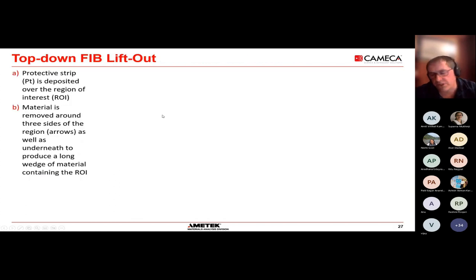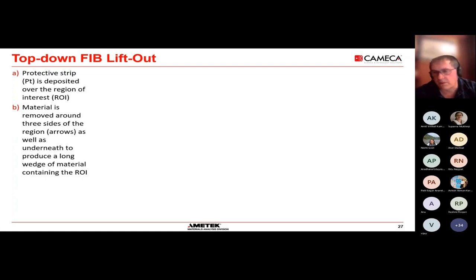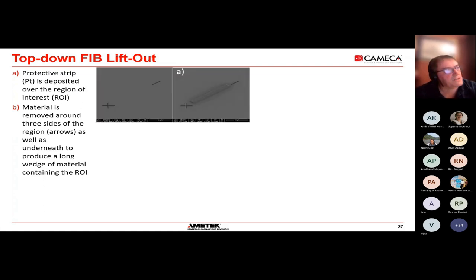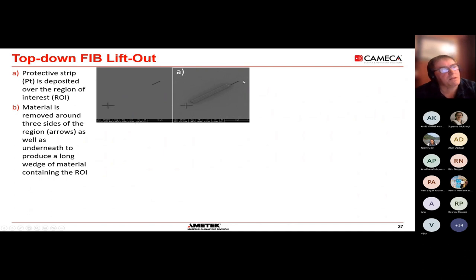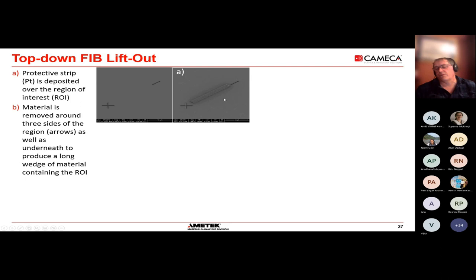A more general method is to use the dual beam FIB. This is an SEM with an electron column — so you can see very clearly what you're doing — plus an ion beam which allows you to make changes in the material and mill features. This has been used classically for the last 25-30 years for specimen preparation. If you can get your piece of material into the instrument, you can make specimens out of it in a very flexible, well-controlled way.